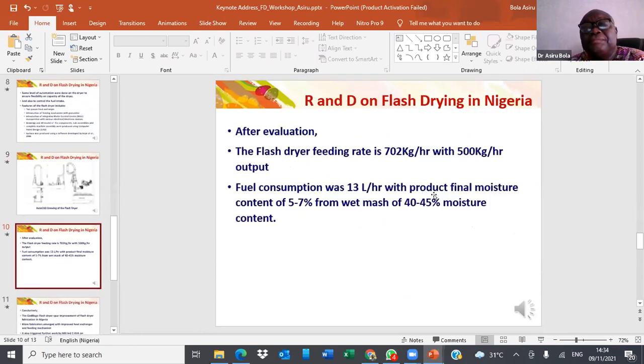After evaluation, the flash dryer feeding rate was planned to be 702 kg per hour with product output of 500 kg per hour. The fuel consumption was 13 liters per hour with product moisture content of 5 to 7% from wet mash of 40-45% moisture content.